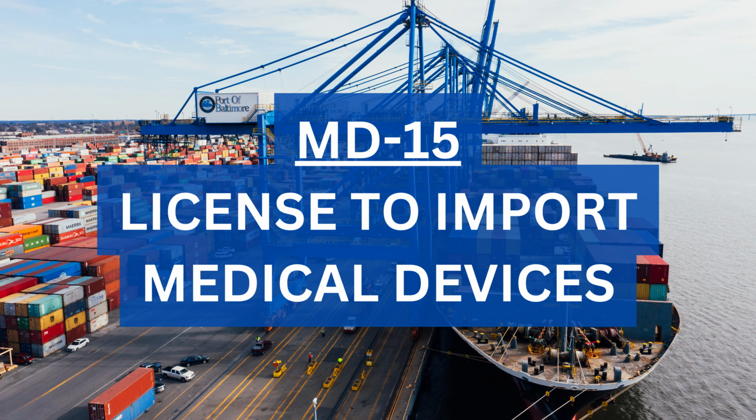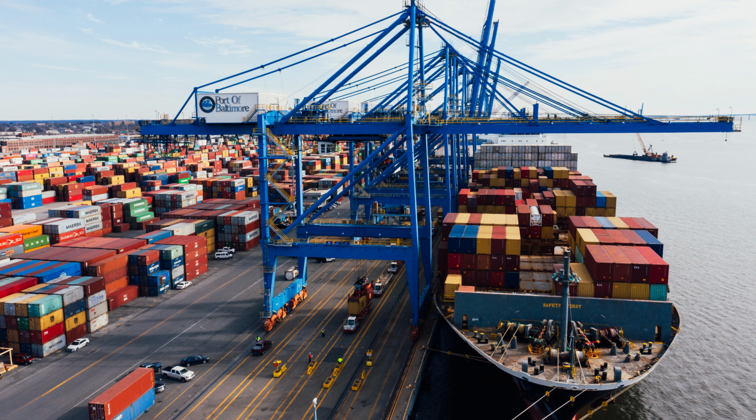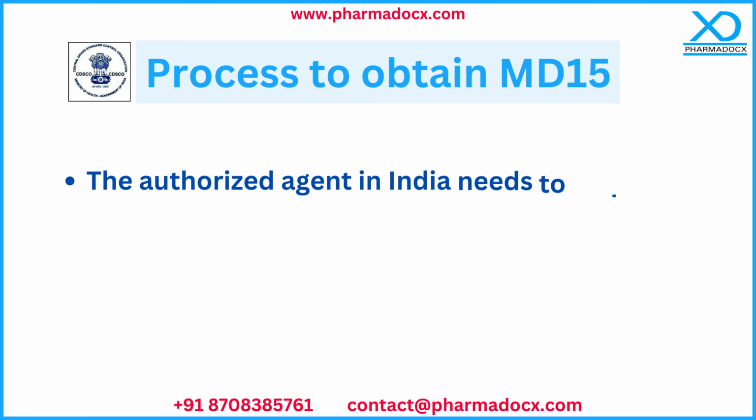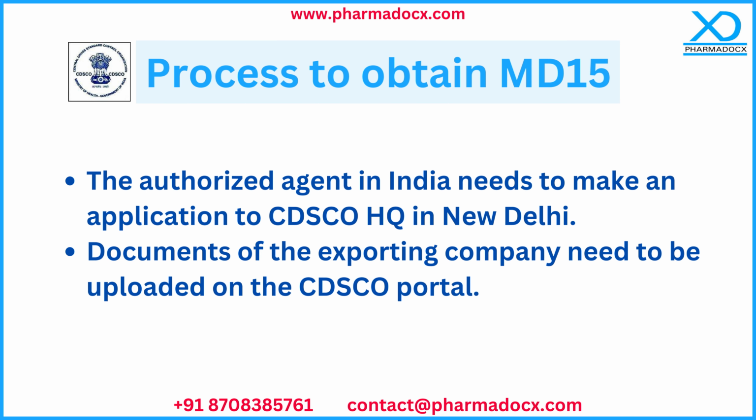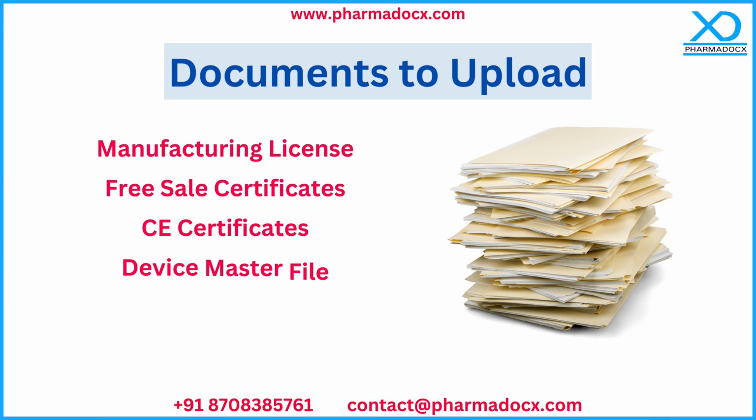In order to import medical devices of Class C and Class D into India, MD15 will be required. The process for obtaining the MD15 license is as follows. The authorized agent in India needs to make an application to the CDSCO headquarters in New Delhi. Documents of the exporting company such as the manufacturing licenses held in the foreign country, the free sale certificates, CE certificates, etc. need to be uploaded on the online CDSCO portal along with the device master file and the plant master file of the product.